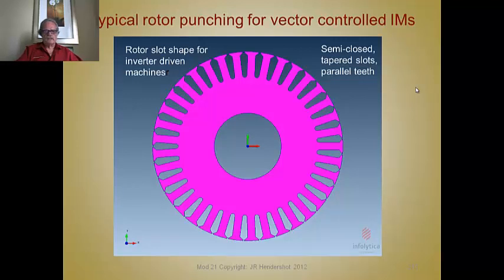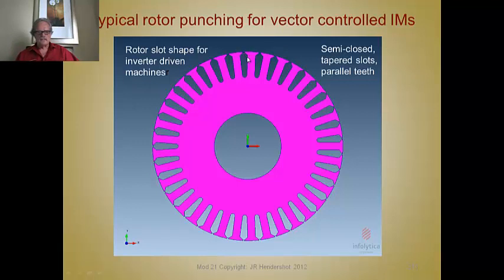Here's a picture of a typical rotor punching designed for a vector-controlled induction motor or inverter duty. Notice the teeth are parallel, the slots are tear-shaped, and the slot openings are semi-closed. The tooth tips are quite thick, and the purpose is to set the angle of the two tips at approximately 45 degrees. That gives a lot of strength in the throat so that the bars can be restrained, and at higher speeds the centrifugal force on the bars — which might cause them to bow or bend — will hopefully be restrained by these tooth tips.